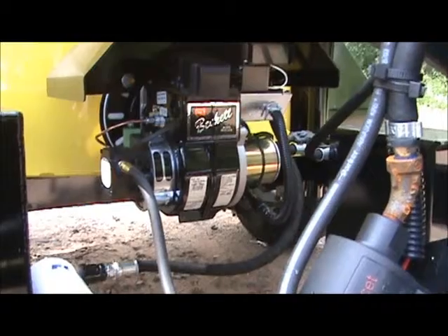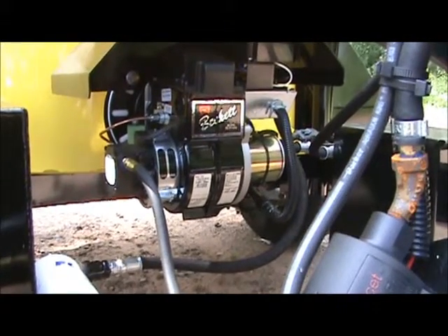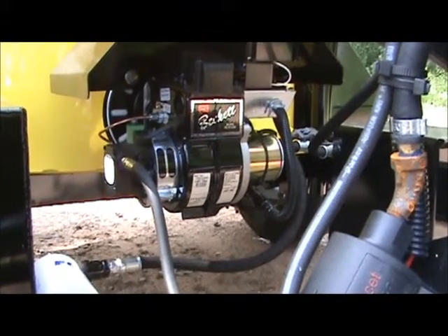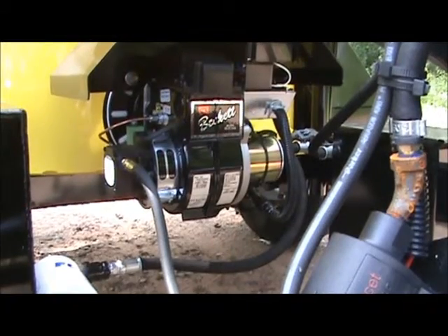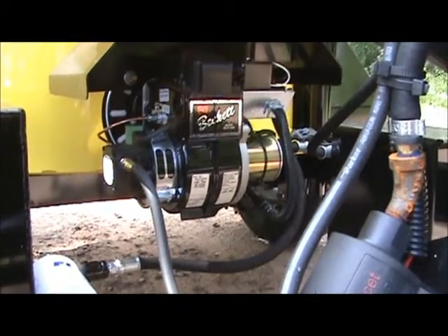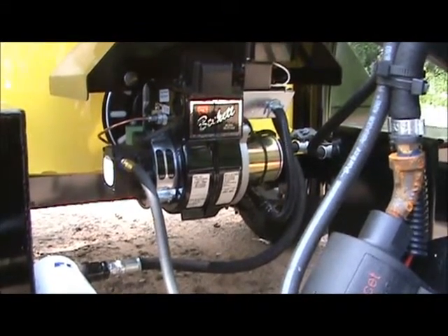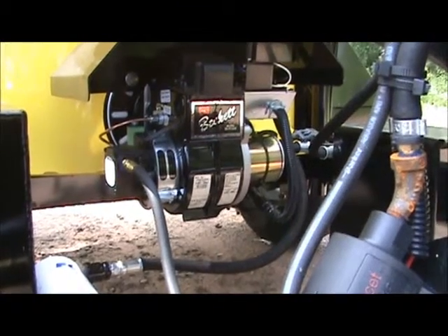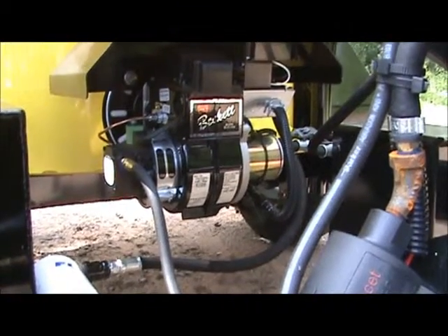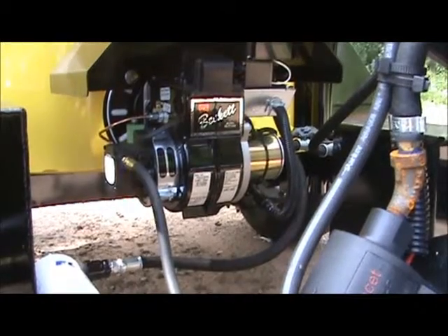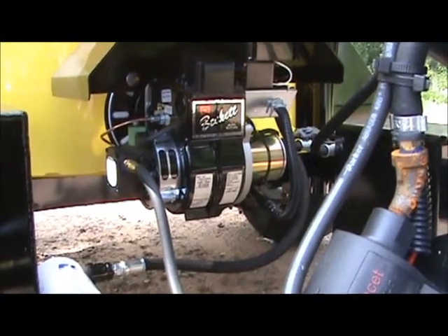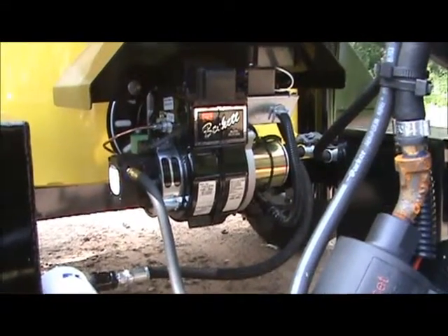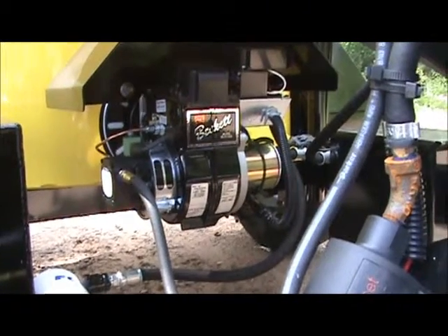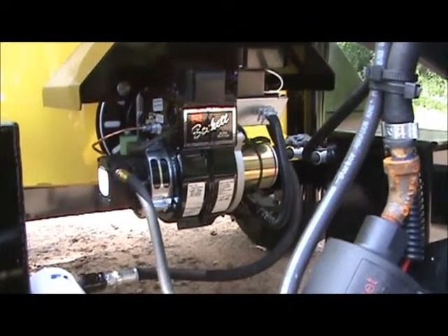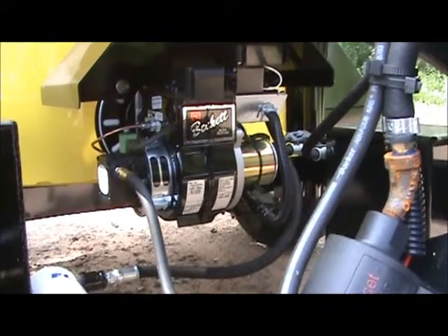Now, reasons it wouldn't fire, one of them would be if it's out of fuel. One of them, if it had an air bubble trapped inside the fuel pump. If there was no spark or no power. Those are all things that are going to tell this thing to lock itself out. If the burner goes into a lockout mode, we have to manually turn the power switch off in the back and turn it back on to recycle the burner. If you try to do that 2 or 3 times and the burner's still not kicking on, we've got to start doing some troubleshooting on the burner.